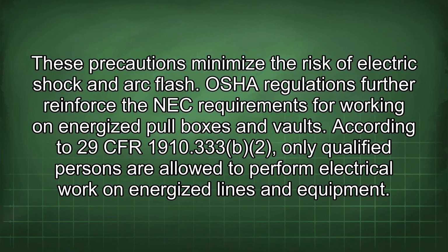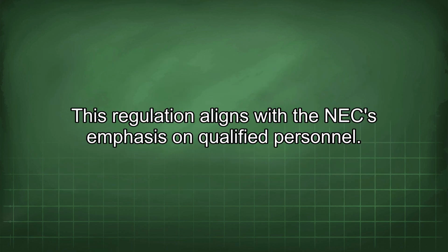OSHA regulations further reinforce the NEC requirements for working on energized pull boxes and vaults. According to 29 CFR 1910.333, only qualified persons are allowed to perform electrical work on energized lines and equipment. This regulation aligns with the NEC emphasis on qualified personnel.